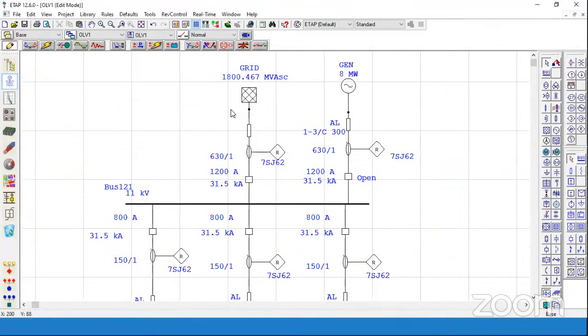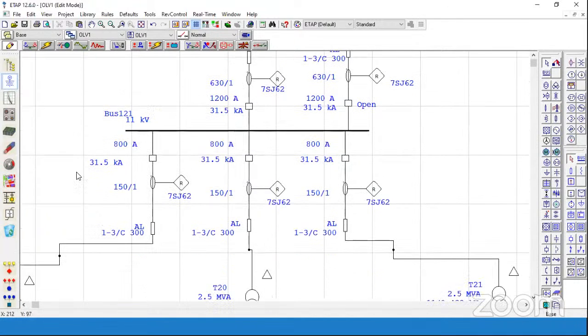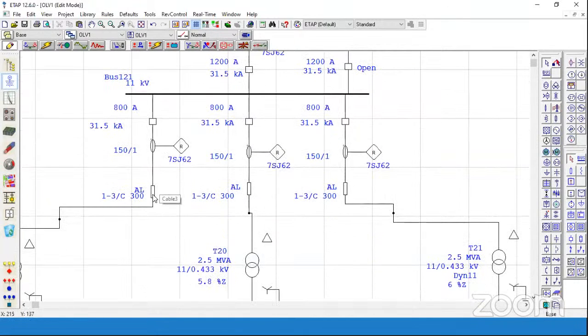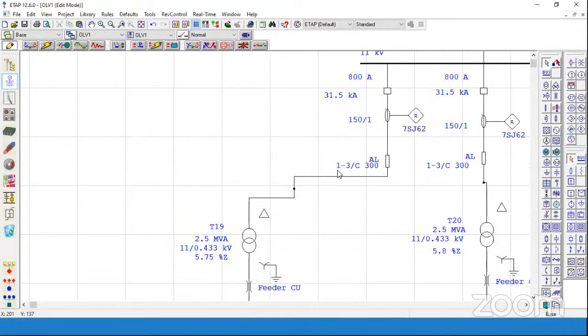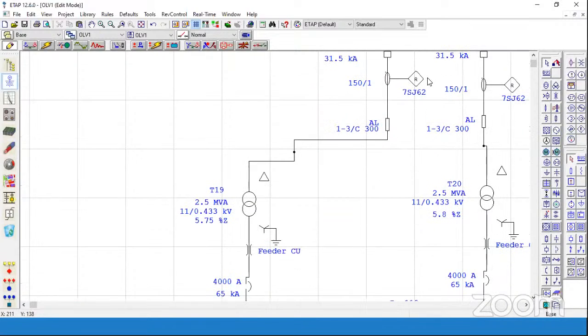So certainly I have modeled every equipment in the single line diagram. The cables I have modeled are aluminum, single run, 3 core, 300 square mm in size. The transformers are of 2.5 MVA. Here we need to input the parameters of the transformers, that is 2.5 MVA transformers. Here it will automatically fetch all the details.